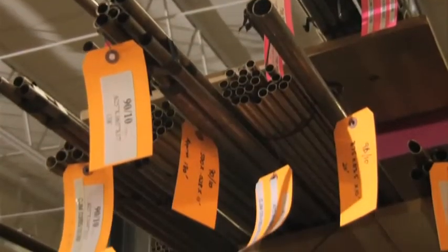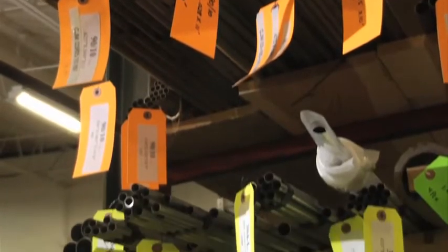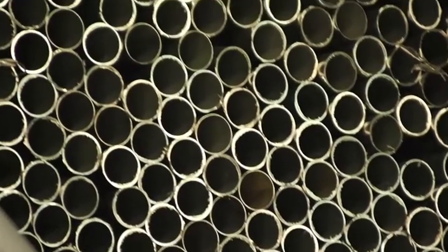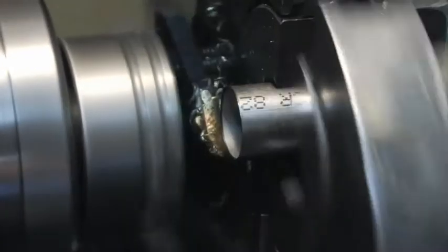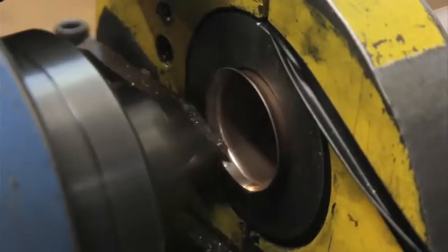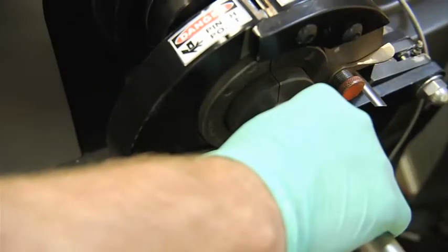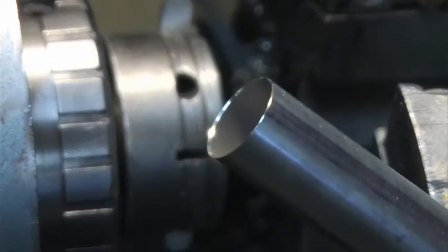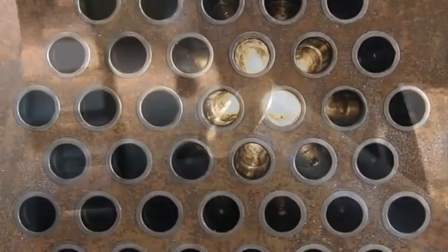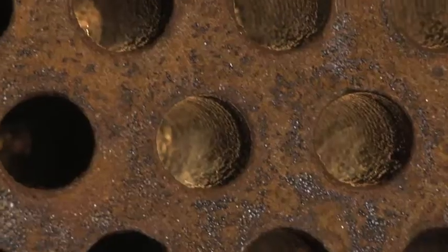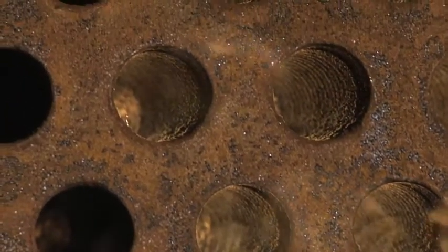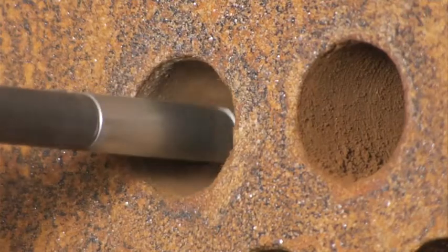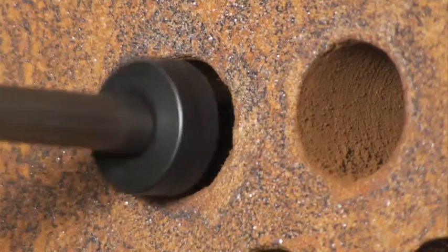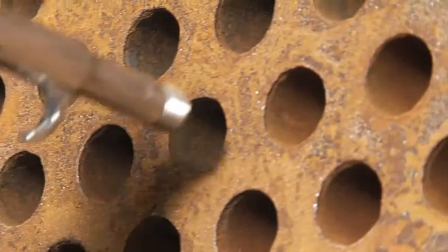Long lengths of thin-walled tubing are shipped to CTI's facility for manufacturing. Tubes are cut to length and deburred. One end is pre-flared, while the opposite end receives an ID chamfer. Our precise fabrication procedures ensure compliance with the quality control specification. Prior to the installation, tubes are thoroughly cleaned. Tube ends are then wire brushed to the length of the shield and blown clear.